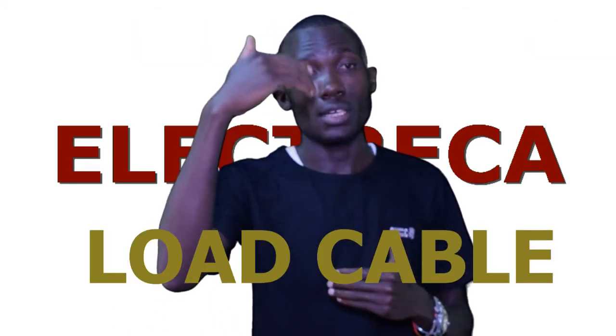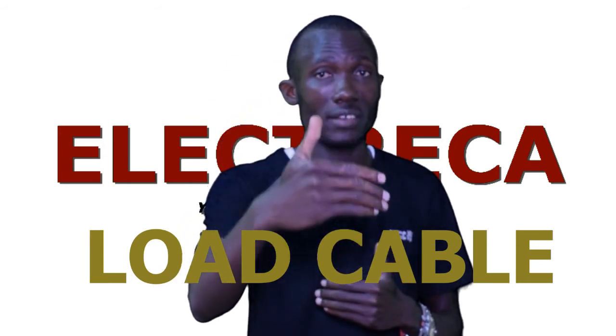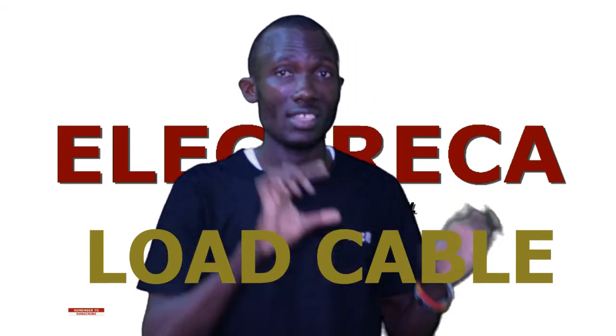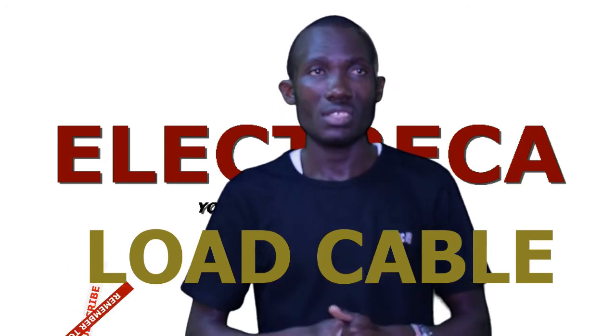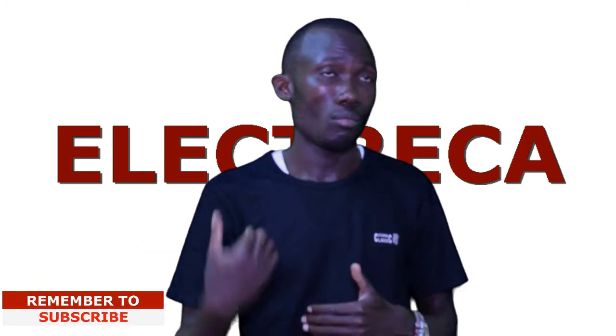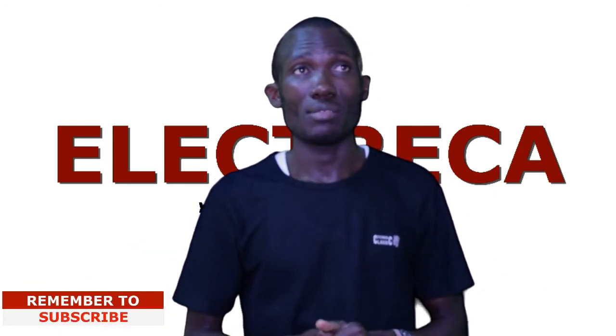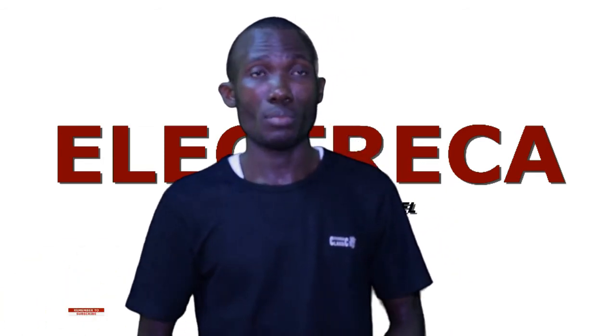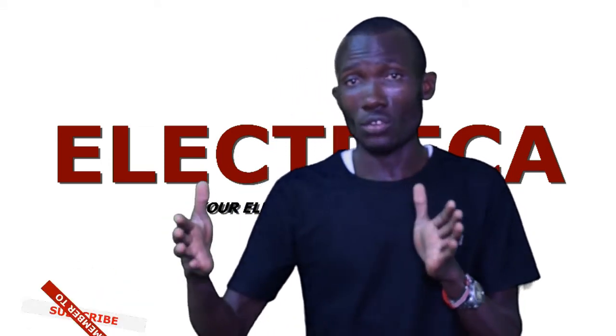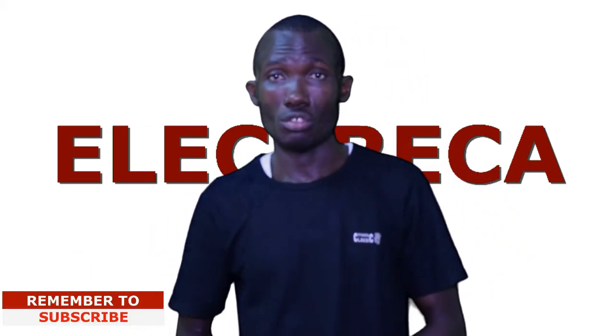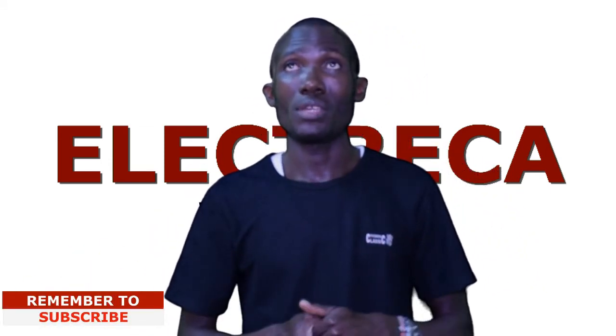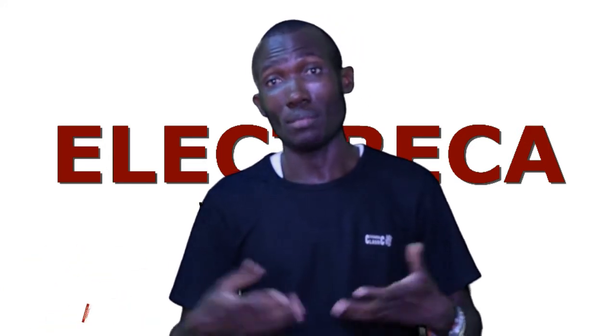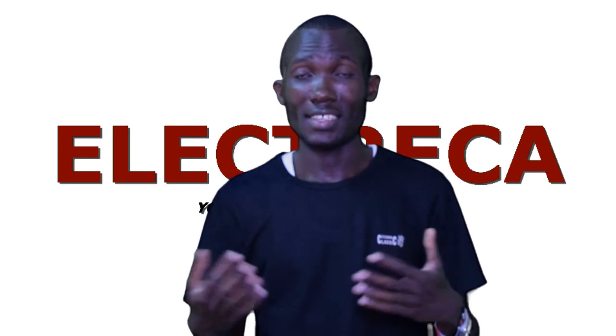Now, the load cable is the cable between your meter box or your metering area to your consumer unit, that small cable. Sometimes that cable is recommended not to be more than 10 meters, but it's really hard to be more than 10 meters because most people keep their consumer unit very close to their metering point. So you find that if it goes further, maybe it will go for 5 meters, but others can even be 2 meters. So the shorter the cable, the better.